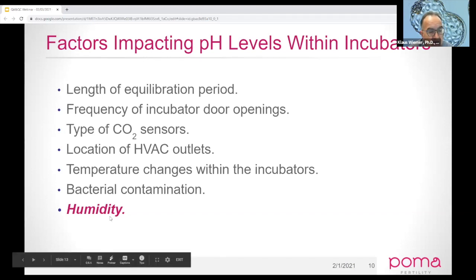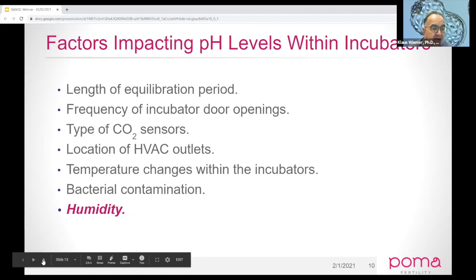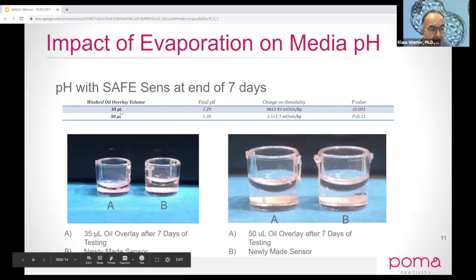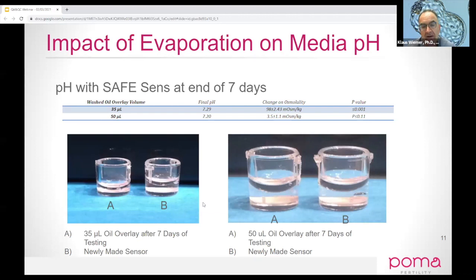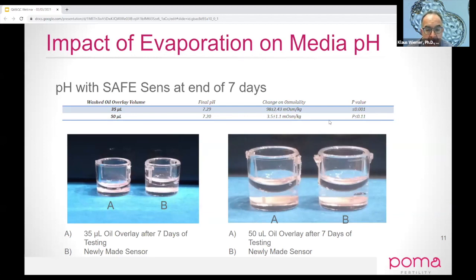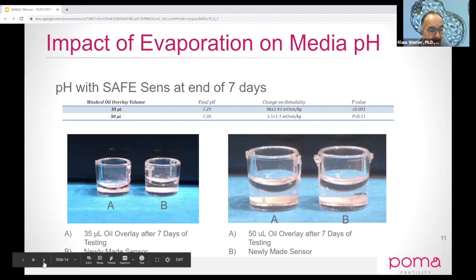One thing I do want to spend some time talking about is humidity. We did an experiment with SafeSense, looking at an overlay of 35 microliters and 50 microliters of oil — roughly how much oil is over the apex of a droplet. When we only have 35 microliters of oil, the osmolarity changed almost 100 units when dishes were kept in culture over seven days. Whereas when we had 50 microliters of oil, the osmolarity change was virtually undetectable — only about 3.5.